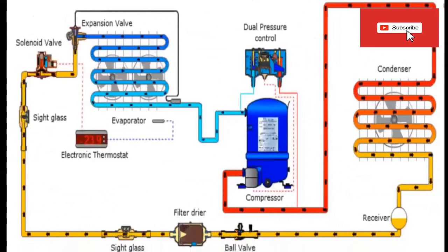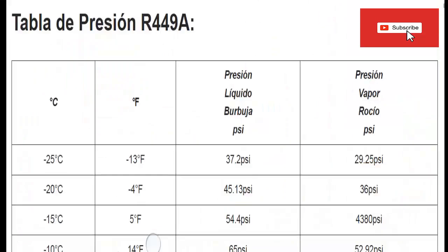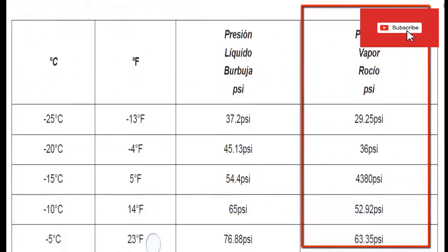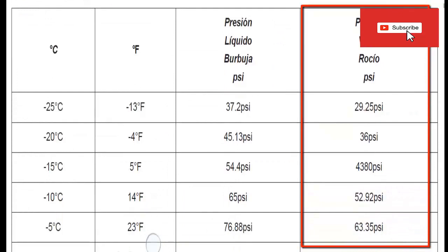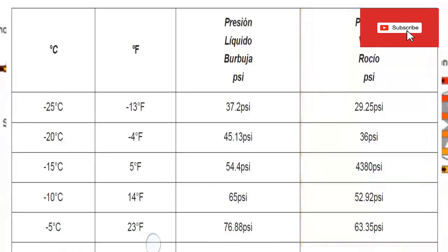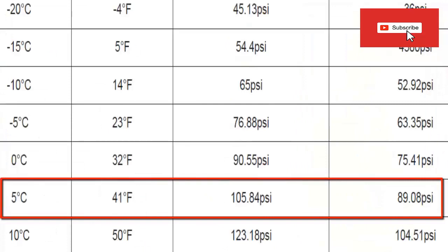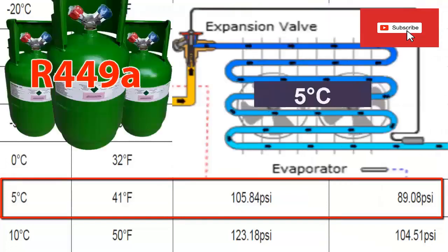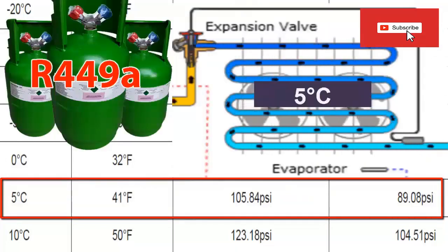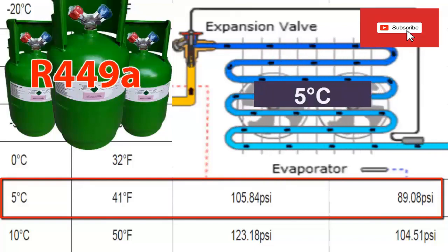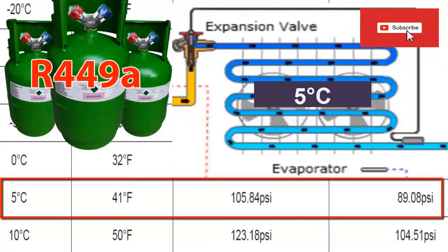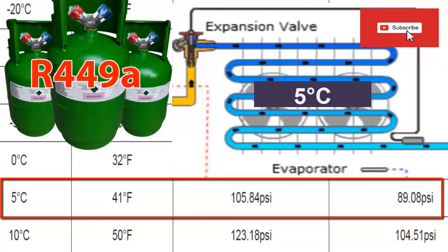Another question may arise: what pressure value is most recommended to work with? In reality, it is more common to work with the dew pressure — that is, to reach the temperature only up to the outlet of the evaporator. However, it is important to note that the bubble pressure is 105.84 psi and the vapor or dew pressure is 89.08 psi. In case of working with an intermediate pressure within these two values, we would be very close to reaching 5 degrees — not at the entrance nor at the exit of the evaporator, but approximately in the middle of the evaporator.